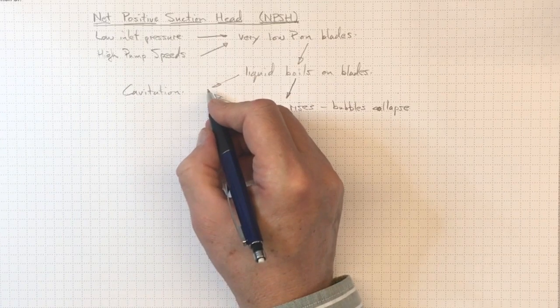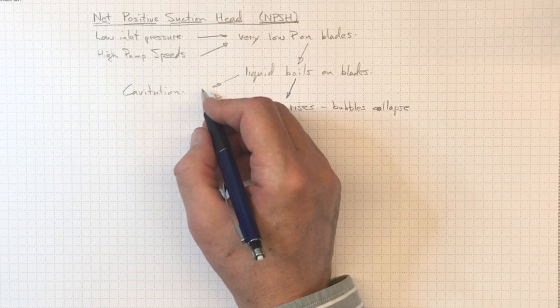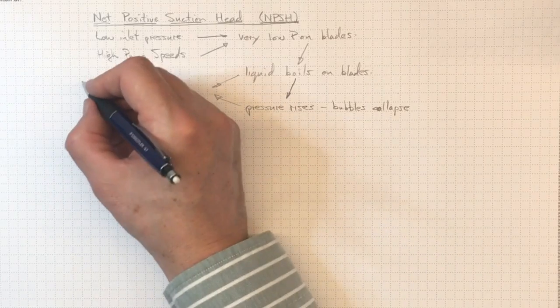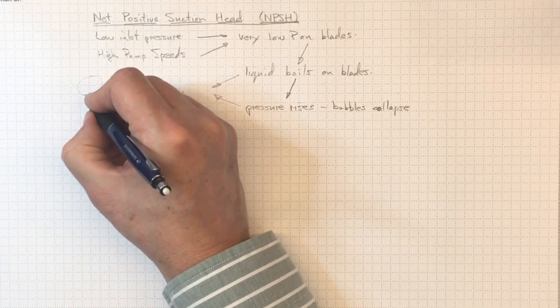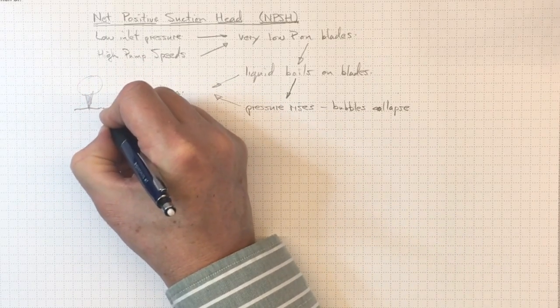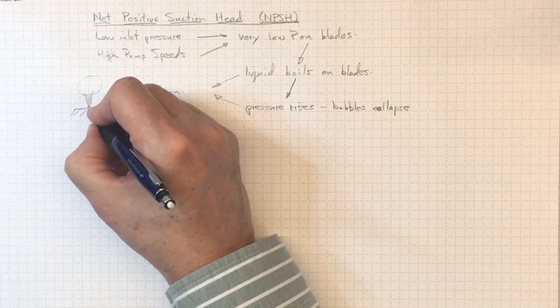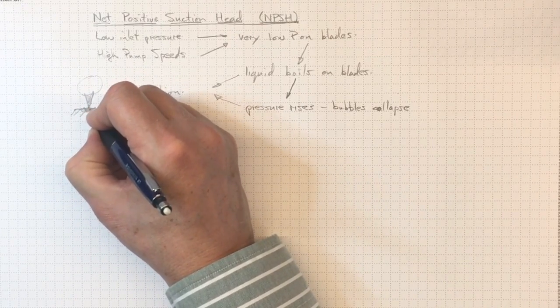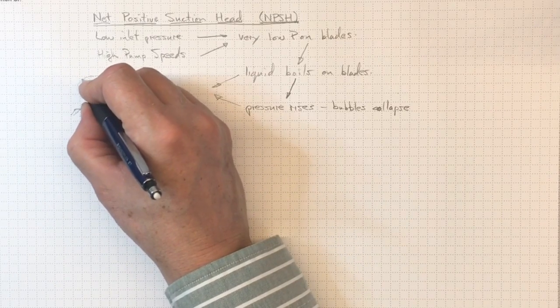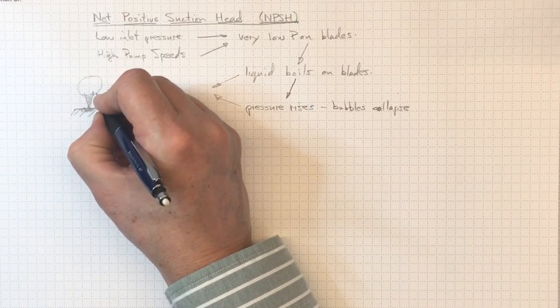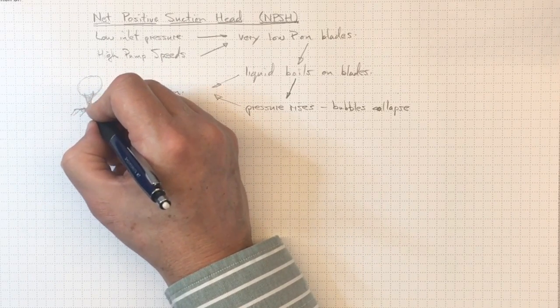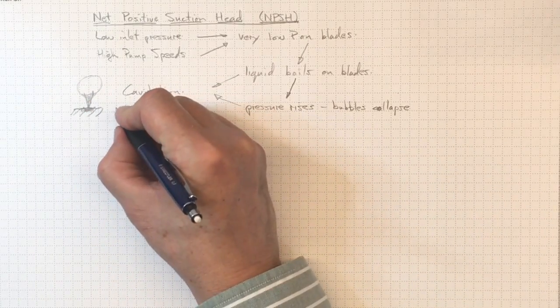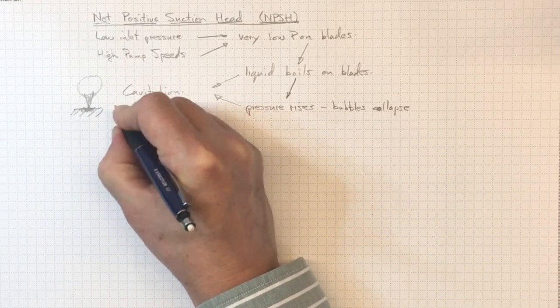It's not the boiling so much that causes the problem, but when those bubbles collapse right next to the blade, a little jet comes down out of the bubble and impacts the blade surface with enormous velocity. That results in damage to the blade and pitting. You can see this in some high speed video that you can find elsewhere on the course website. So that cavitation leads to impeller damage.